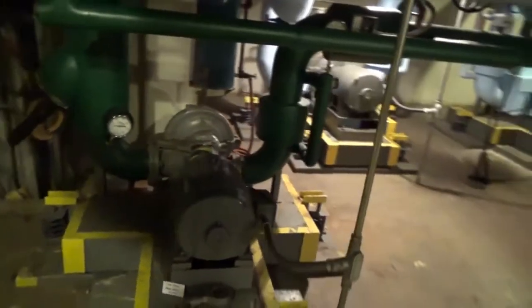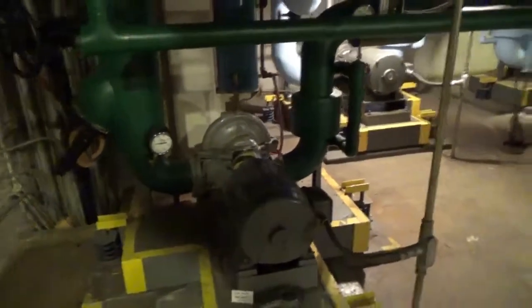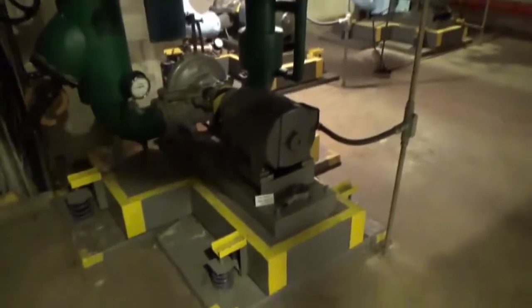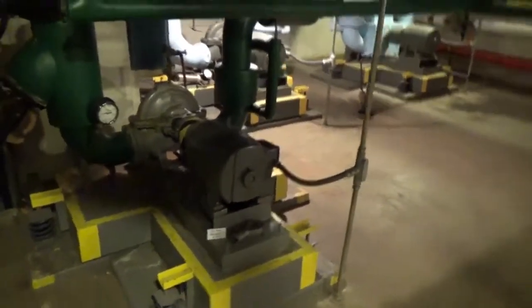It should probably be exercised at least twice a year, every 6 months or something, so we don't have a problem opening and closing those valves, or it's not a surprise if the pump doesn't run. So we'll have to get that on some sort of PM program.